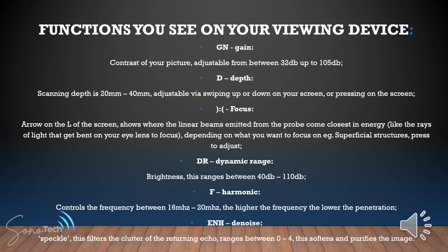So some of the functions: GN on your screen will stand for gain. This is the contrast of your picture. Because we're talking about sound waves, it ranges between 32 decibels all the way up to 105, these are all adjustable. Your D standing for your depth. Your scanning maximum depth is up to 4 centimeters. This is adjustable either by swiping up or down on your screen itself or by pressing the function for depth. Your next one is focus. There's a little arrow on the left hand side of the screen. And that shows where the linear beams emitted from the probe itself come closest in energy, almost like the rays of light that get bent in your eye lens to focus. This then depends on what you're looking at. Is it superficial structures or is it something deeper down? This you can then adjust.